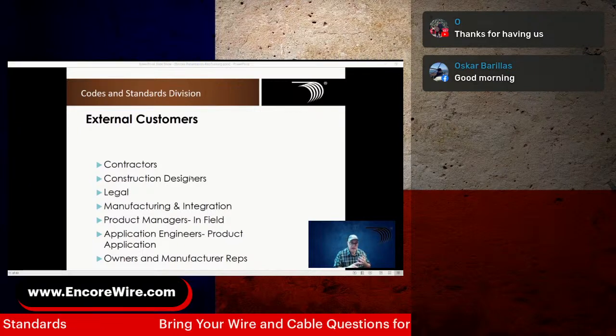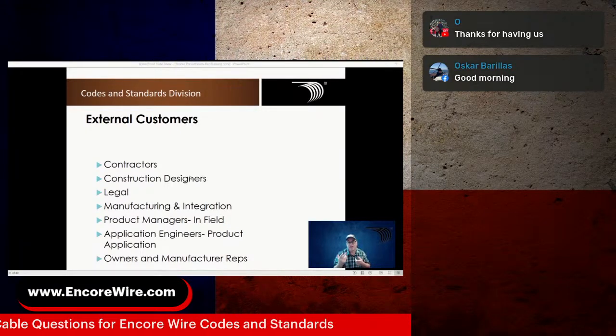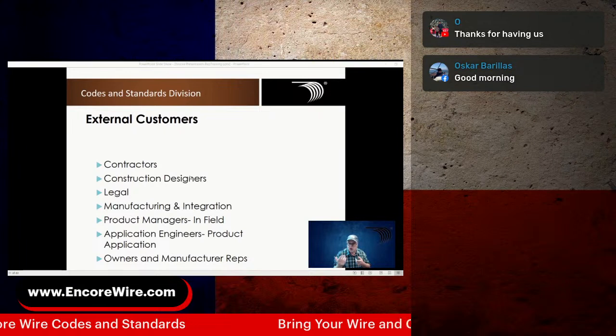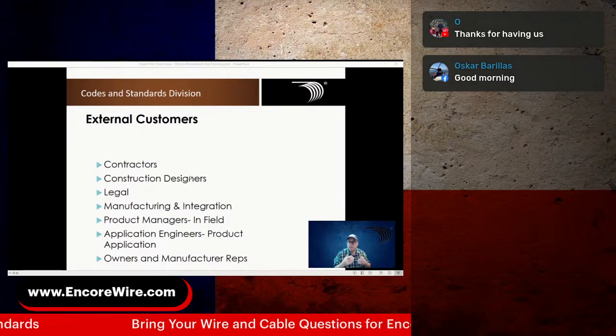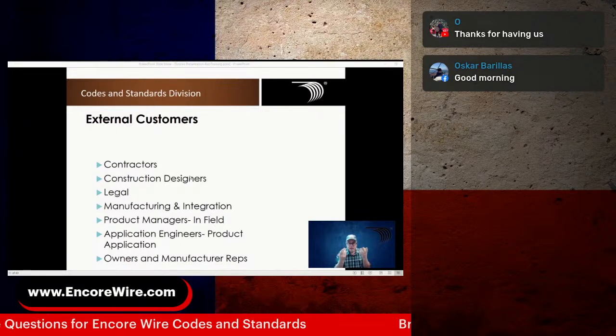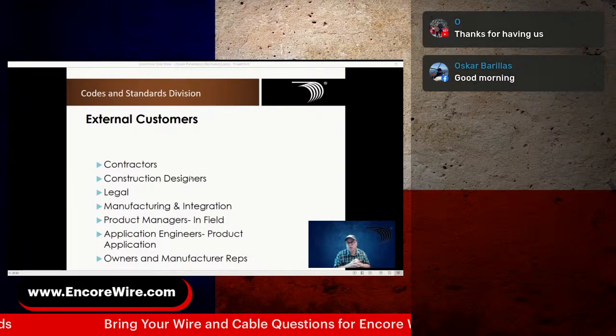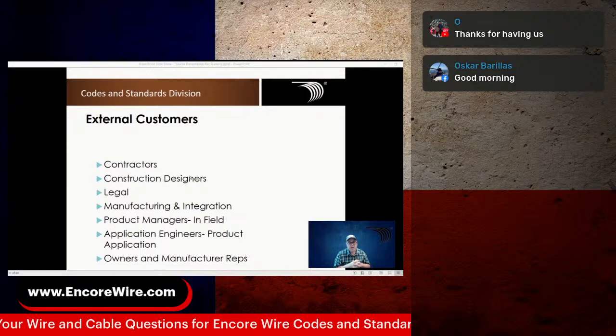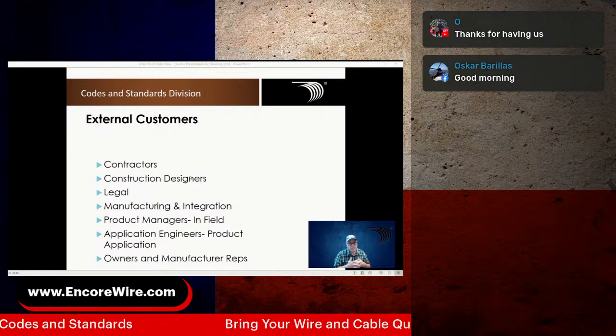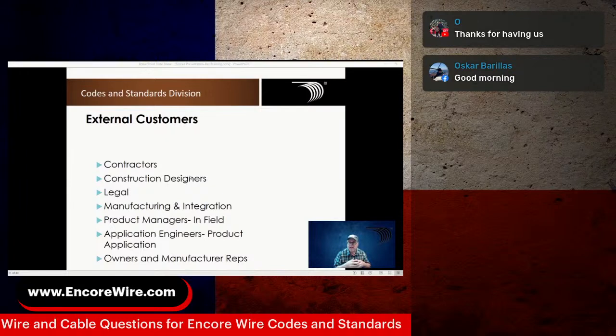When can you use tray cable? When can you not use tray cable? Can I run MC cable? What about SE cable? I did mention that earlier. We make SE cable, SEU, SER, and we even make the new hybrid that is a cross between SER and tray cable, so it has unique benefits of both. We're asked those questions all the time from the end user. Application engineers will call us up and want to know what product to use for a certain installation, and we'll give them all the options. They have to make the decision, but we'll give them those options.